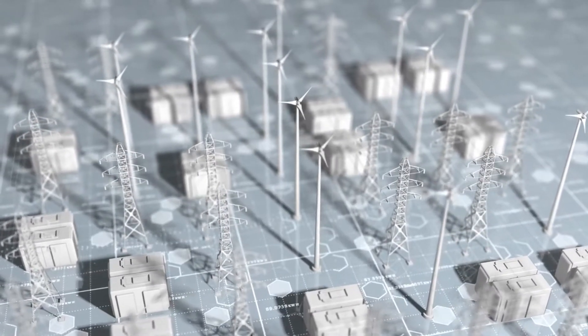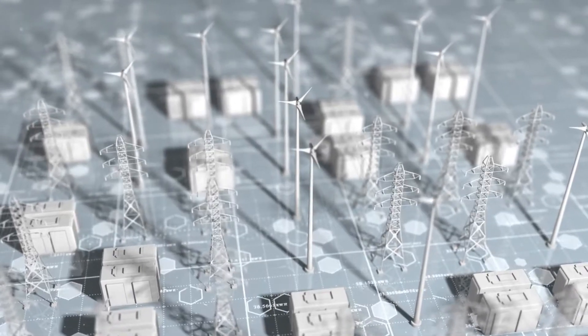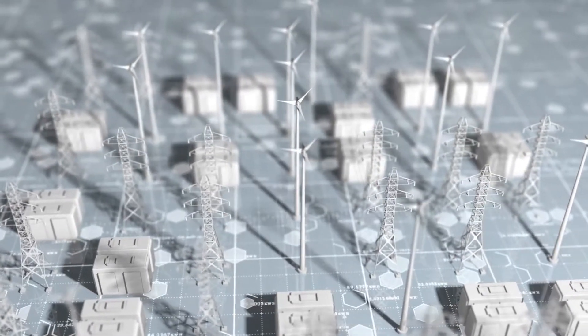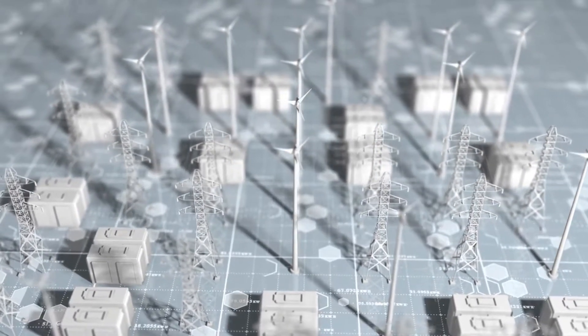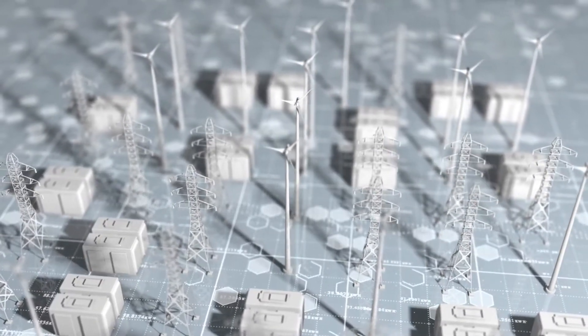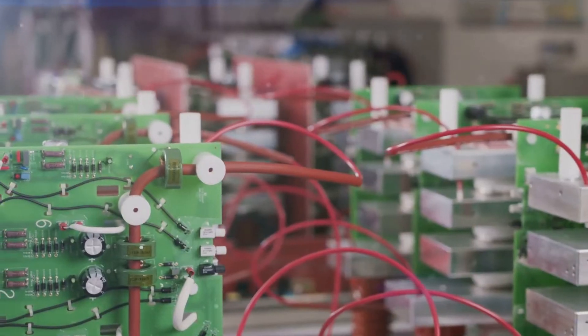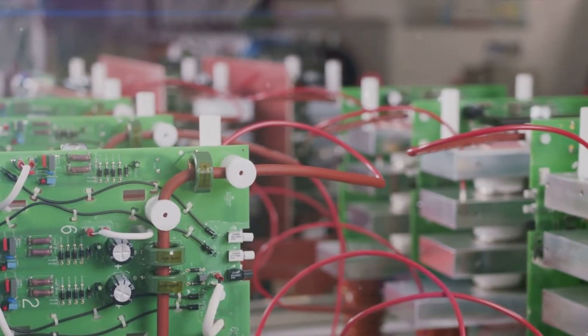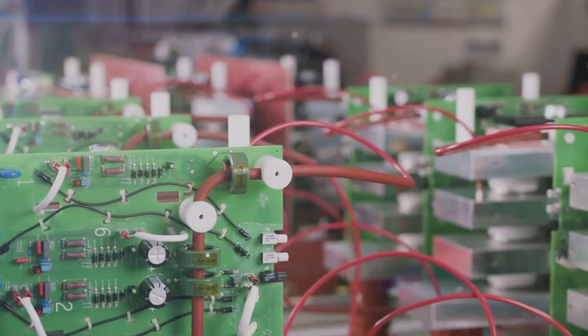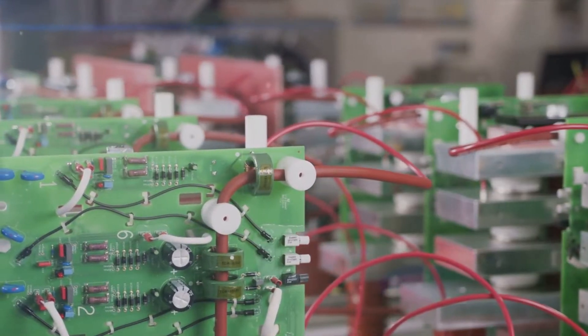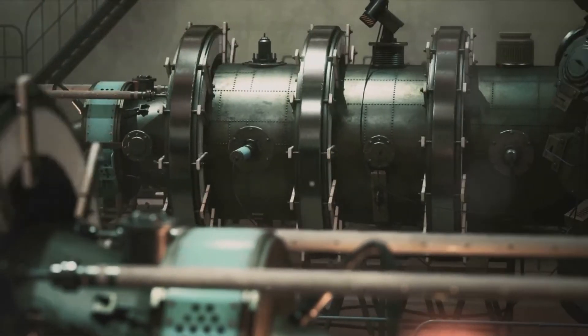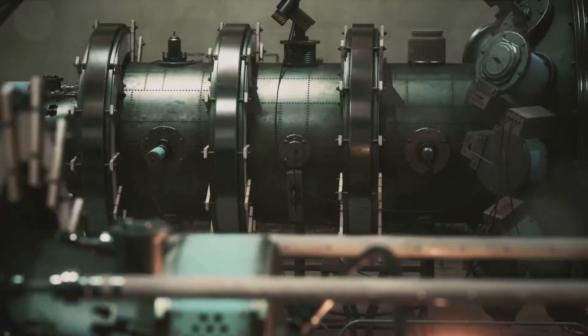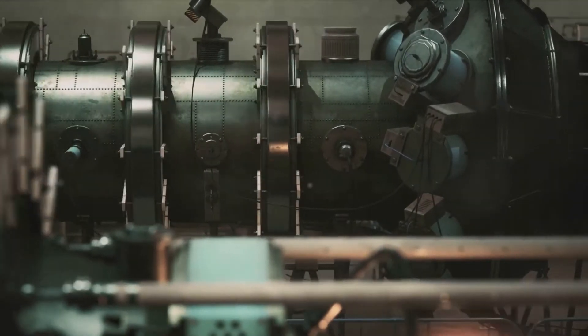Let's start with capacitor banks. These are clusters of capacitors connected together in a power system. Capacitors are devices that can store and release electrical energy rapidly. In power systems, they are used to provide reactive power. When the power factor dips, capacitor banks inject reactive power into the system to balance the equation. This helps maintain voltage stability and enhances the overall system efficiency.